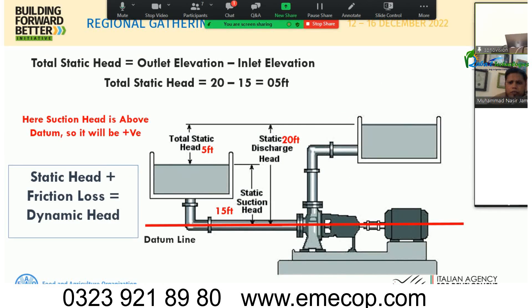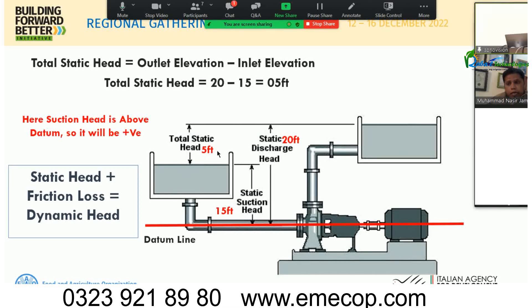In another situation, when water is drawn from a reservoir above the datum — for example, 15 feet above the datum — and needs to be carried to 20 feet above the datum, the net head to work against is only 5 feet. That 5 feet is the static head, and adding friction losses to it gives the total dynamic head.